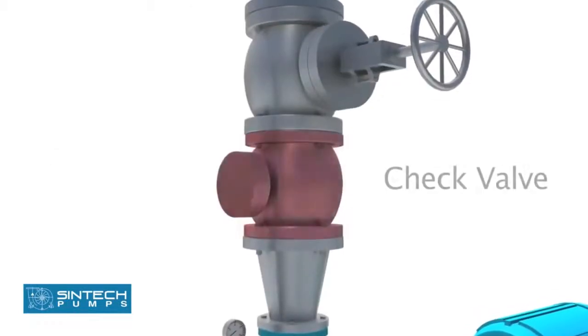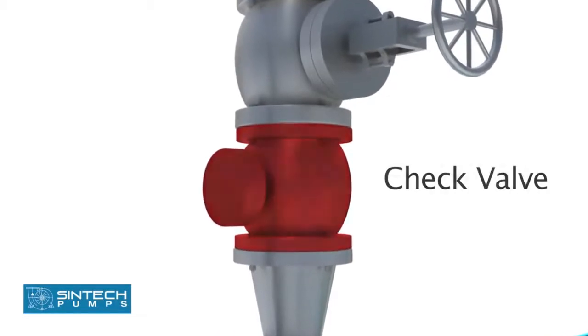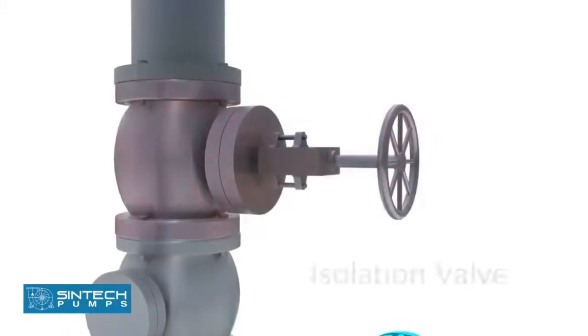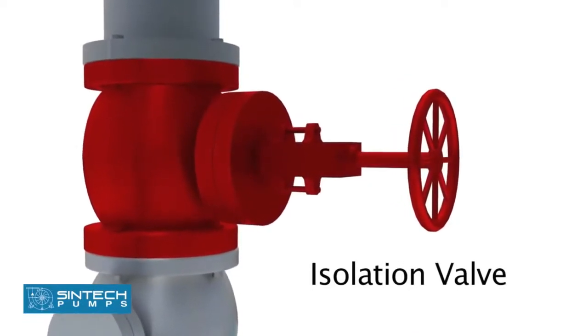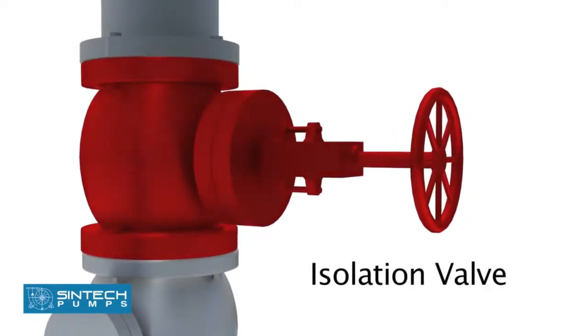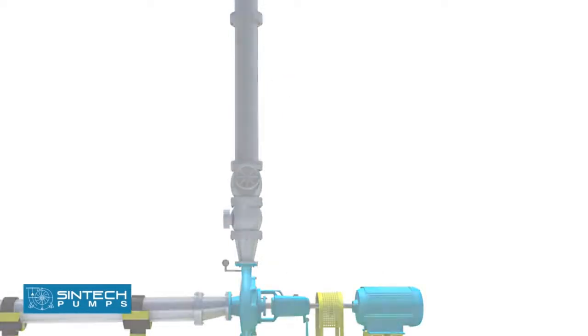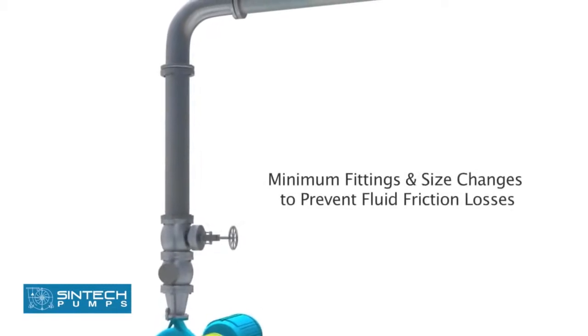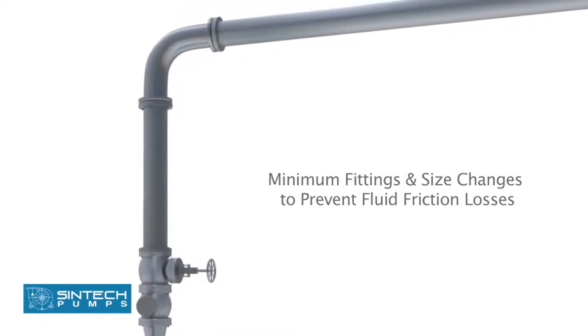The check valve used in the discharge should be of non-slam type to prevent hydraulic shocks. The isolation valve is provided downstream of the check valve so that these can be taken up for servicing whenever required. Discharge pipe size should be at least one commercial size larger than the opening of the pump outlet. The number of fittings and size changes should be minimum to prevent fluid friction losses.